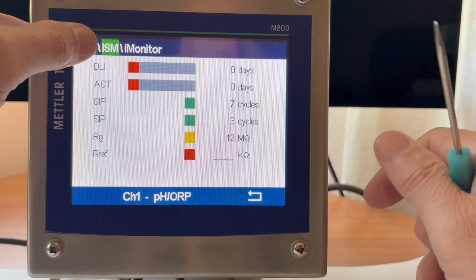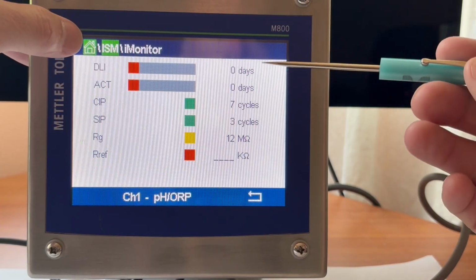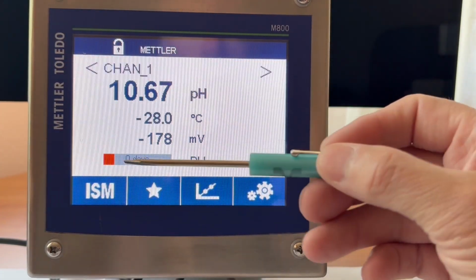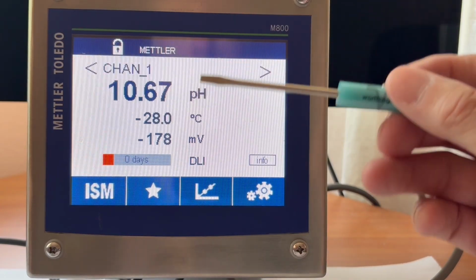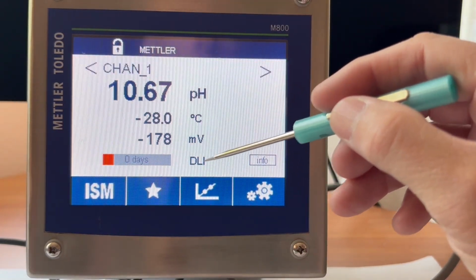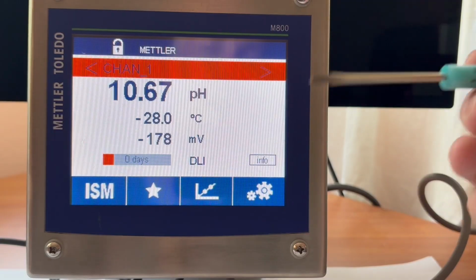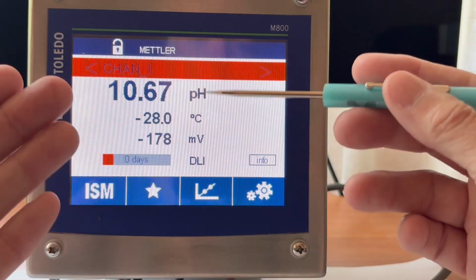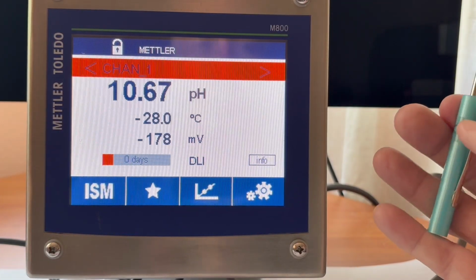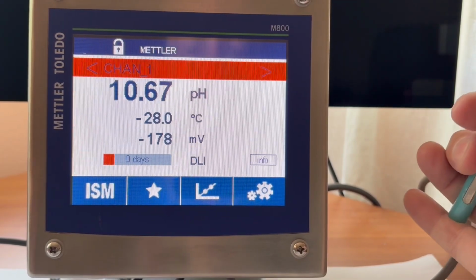So again, you actually will have numbers of days presented, even on the display if you set it up that way. And this could also be sent through 4 to 20 on the analog outputs, or if you're using Ethernet or field bus, all of that information is carried through on the digital bus platform. So you could see this in a control room.